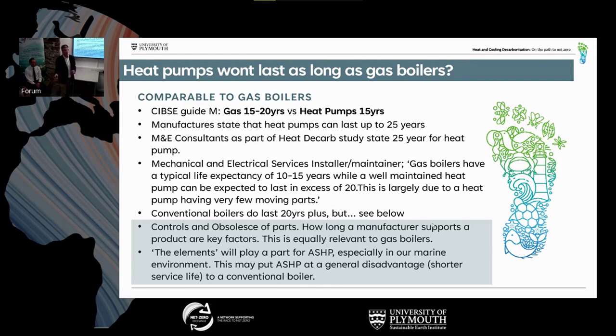If a manufacturer is supporting that gas boiler or heat pump for a long period, it's going to last longer. The reason I'm having to replace the Portland Square heating system is because the controls failed on the boiler, and I've got no way to fire them up - it wasn't that the boiler was physically broken, it was the control. That could happen to a heat pump too, I suppose. But I thought there's a law against not providing parts over years and years. Once you get to, say for the Mary Newman boilers, 20 years, there's probably a point where that's not supported - certainly not good enough.